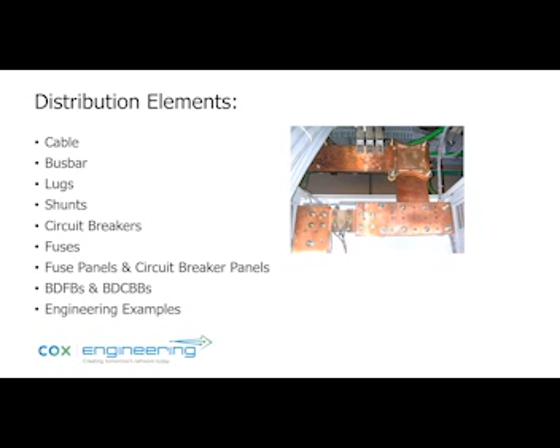So the cable within a critical facility, you have to make sure that it's V-0 rated, in terms of fire suppression and all that, low smoke flame. THHN is generally frowned upon, at least for the large cable. And that's THHN, your standard AC power cable. So RHW or RHW2, you may have seen them.